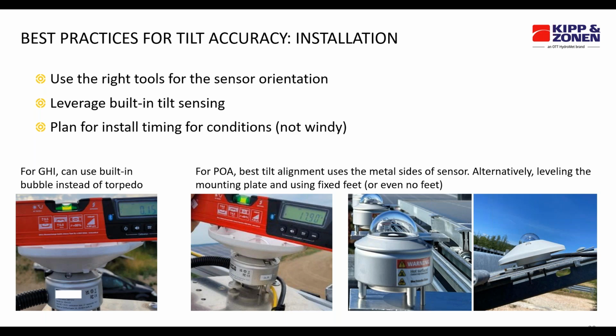Rather than getting creative on how to measure the north-south and east-west alignment of the sensor, it can be kind of challenging to get a level onto the sensor body, or, as you can see here, using something that may have imperfect plastic, even though visually it looks pretty close. As we've seen, even 0.2 degrees really makes a difference. So we want to make sure that we're doing everything we can to get these pointed the way that we want them.